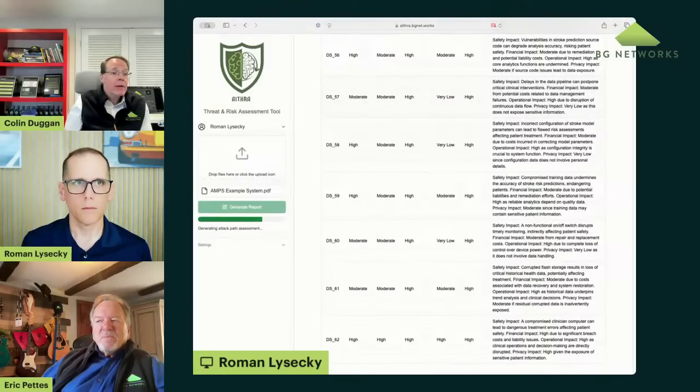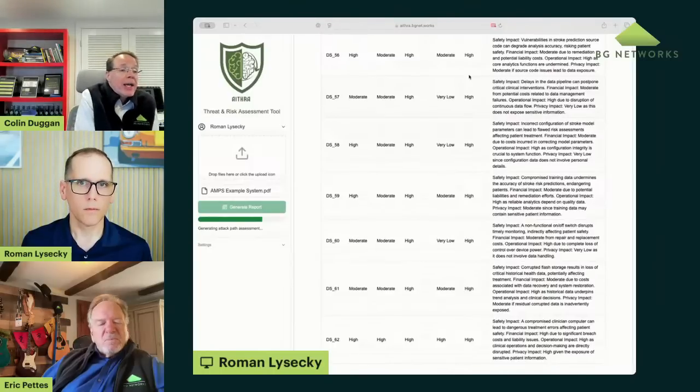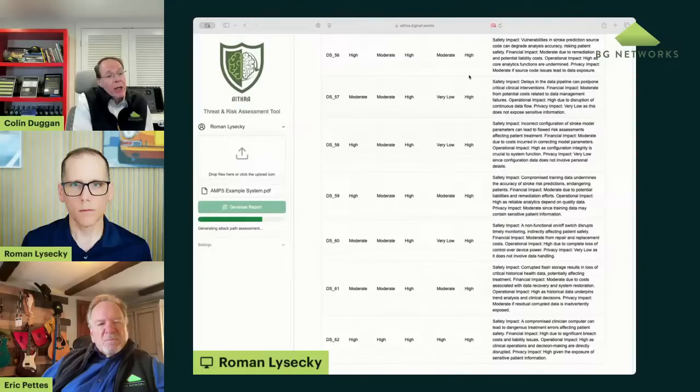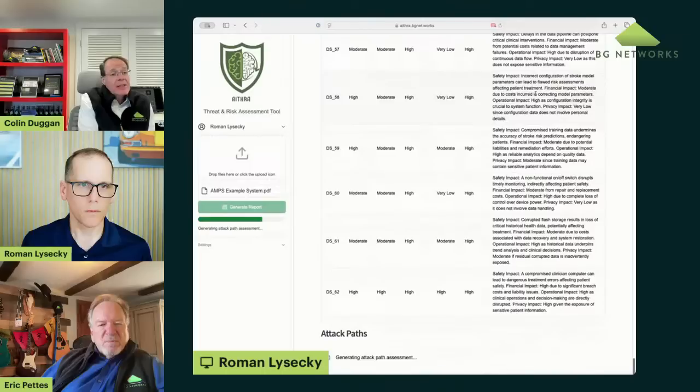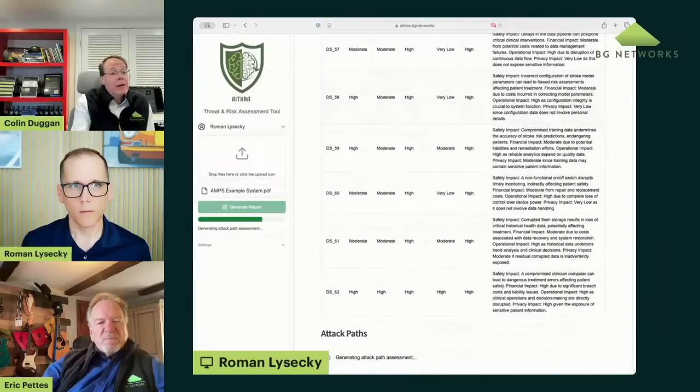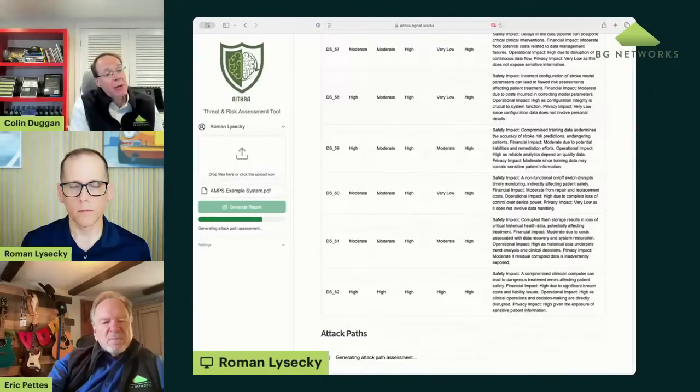After you do your pen testing, you're going to want to go back to the threat and risk assessment again. And then after you look at your unresolved anomalies, features that may impact cybersecurity, you'll want to run those through the threat and risk assessment again. And the FDA is going to expect you to do that if you're making a case to not fix because you're going to say they don't impact, or even if you're going to put a mitigation in, to justify what the mitigation is, you're going to want to have that threat and risk assessment evaluation.